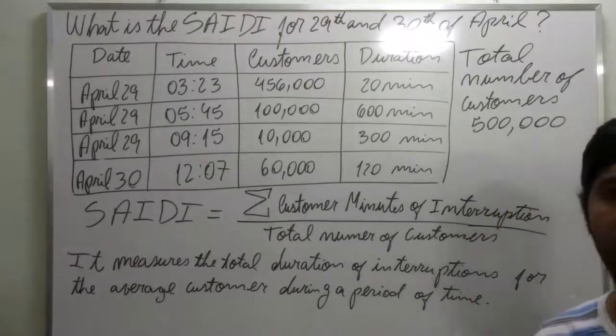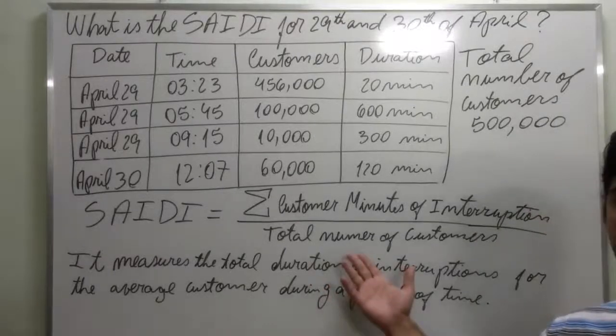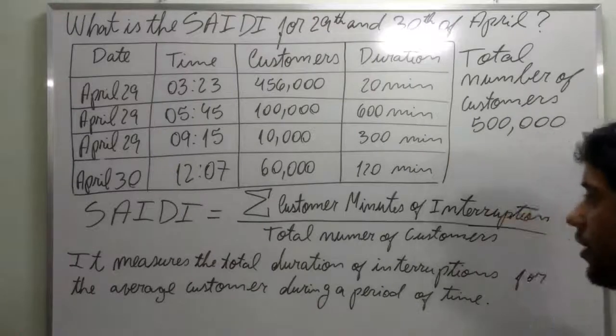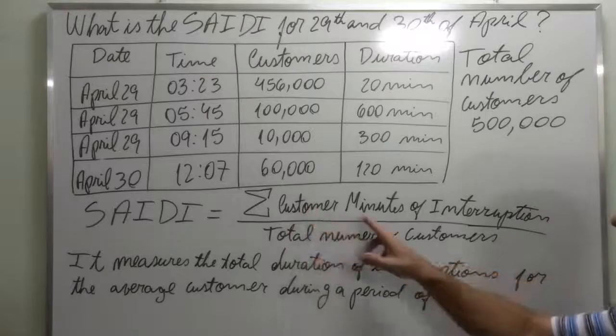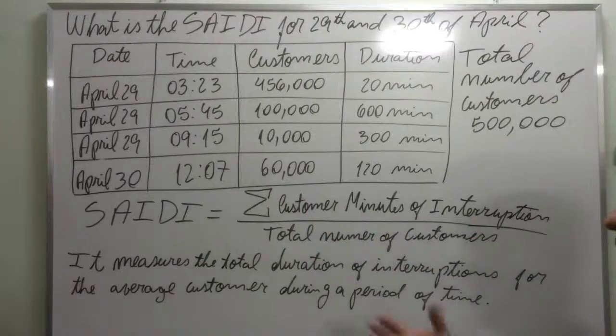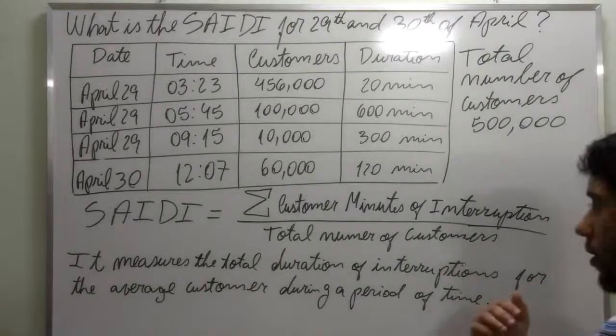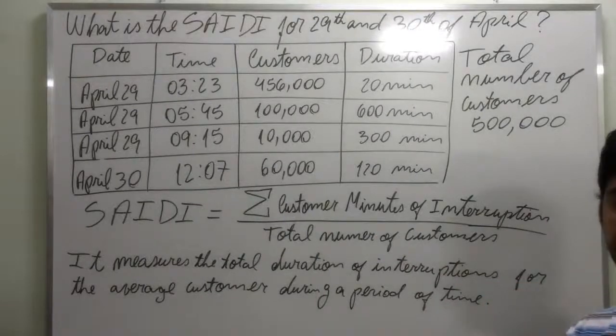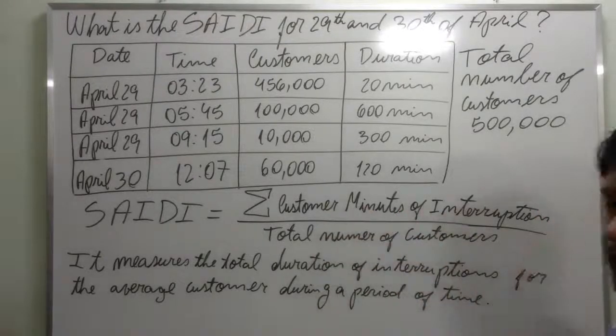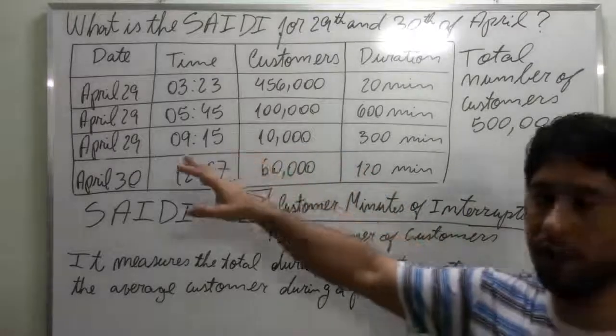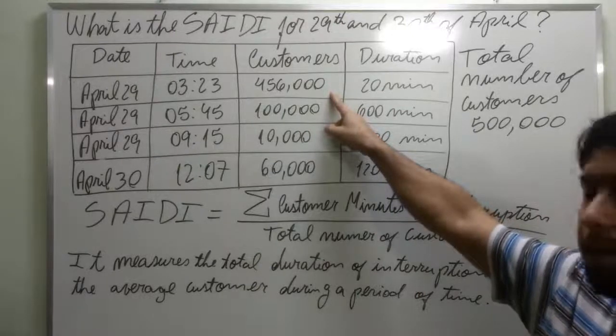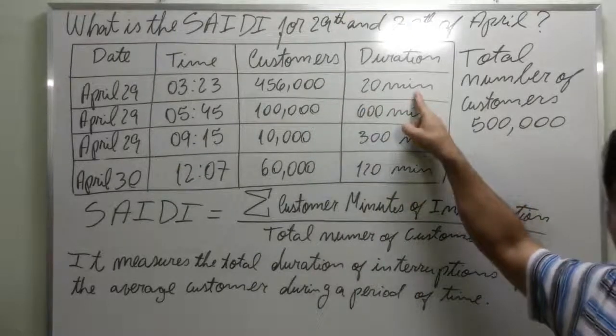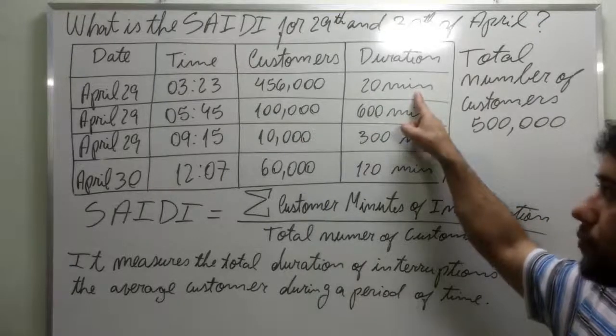We calculate this index using the expression provided by IEEE. This expression says that we need to compute the customer minutes of interruption and divide by the number of customers of that area of concession of that utility. Customer minutes of interruption is the product between the number of customers interrupted by that outage and the duration of the interruption.